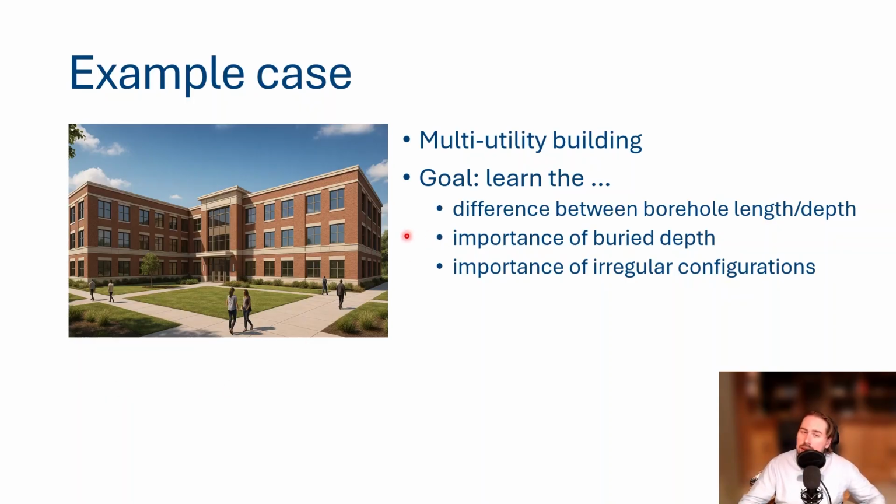We will be also looking at the importance of the bury depth. Now, in not all software tools related to borefield design, this is an important or required parameter, but in GG2 it is. And we will discuss how it influences your final design. And then, last but not least, we will be also talking about the irregular configuration itself and why it can be important to use the real coordinates of your boreholes instead of just using standard configurations and how this impacts your results.